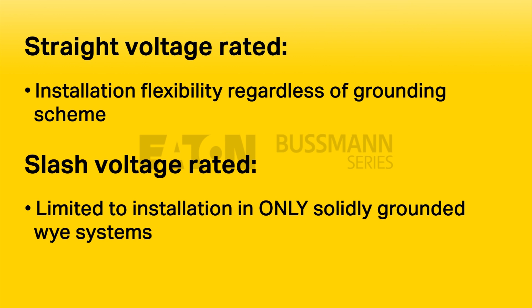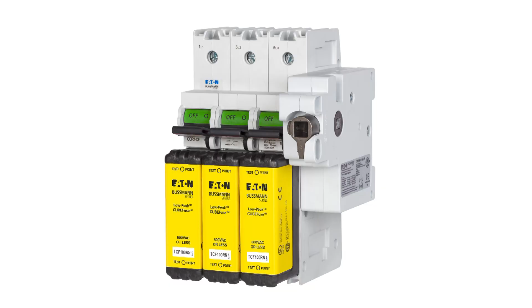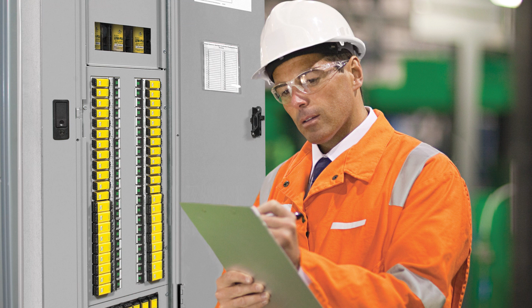by federal law. Fuses are straight voltage rated and provide flexibility to be installed in any system regardless of its grounding scheme. A slash voltage rated overcurrent protective device is limited to installation in only a solidly grounded Y system. Modern current limiting fuses, such as the Bussmann Series Cube Fuse, are finger safe. When used with the compact circuit protector and in the QuickSpec coordination panelboard with door-in-door construction, risk of electric shock is minimized by reducing exposure to live parts when replacing the fuse.